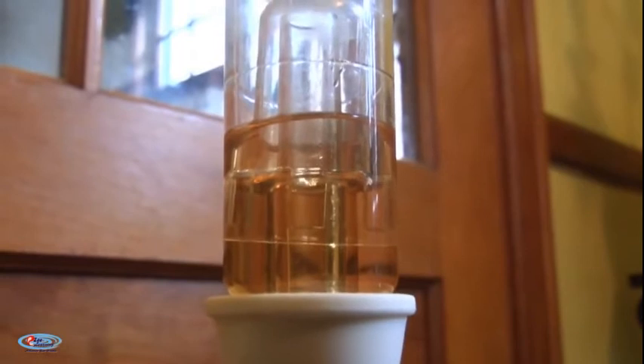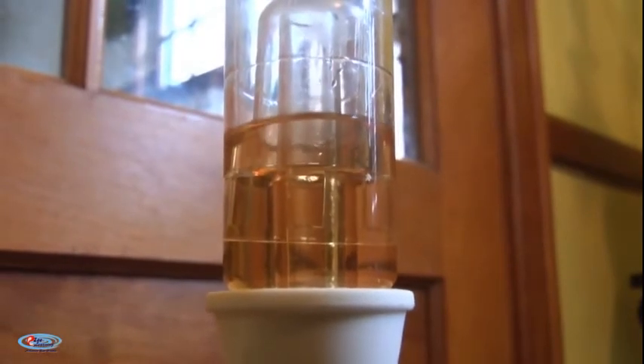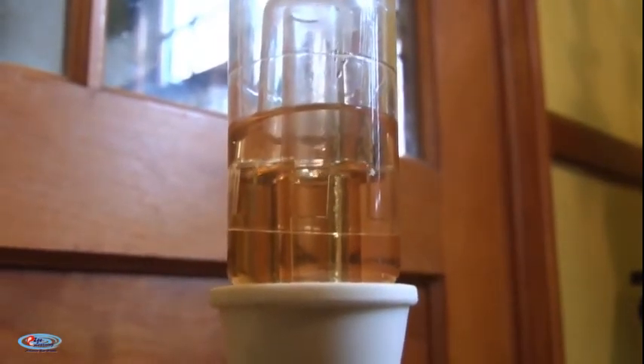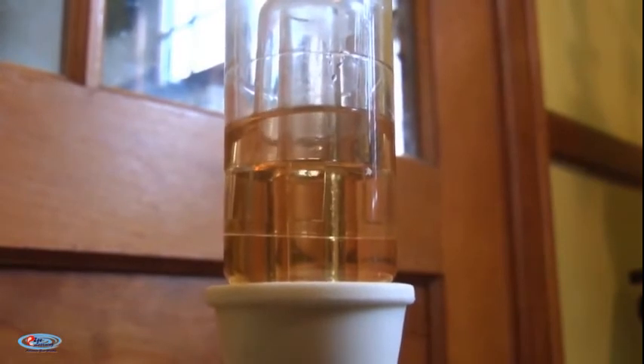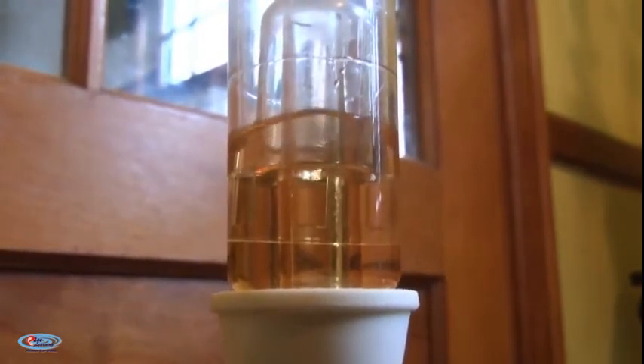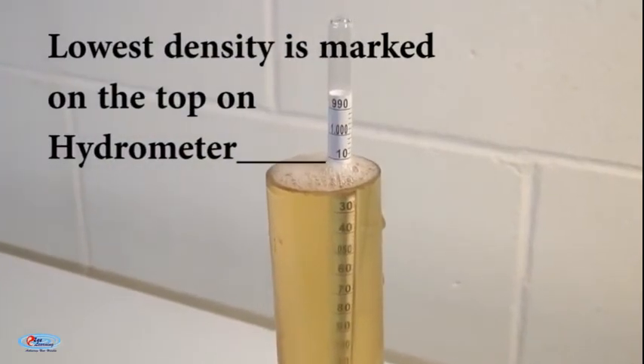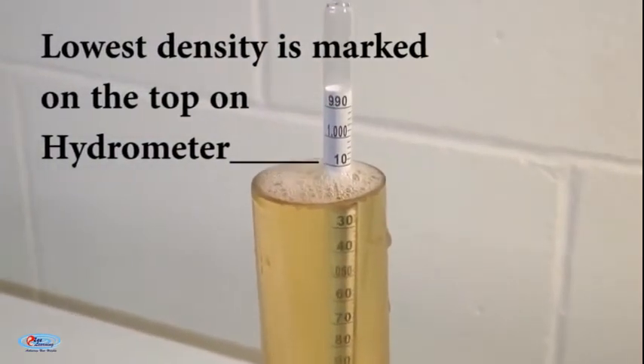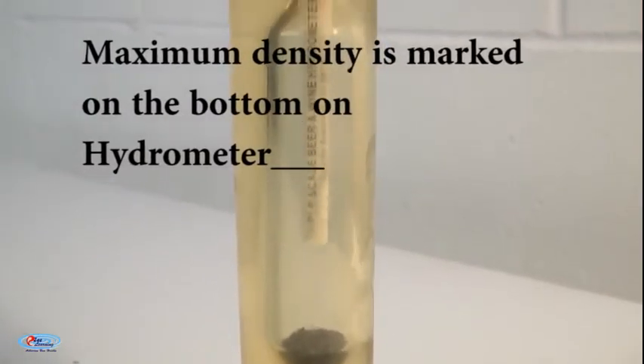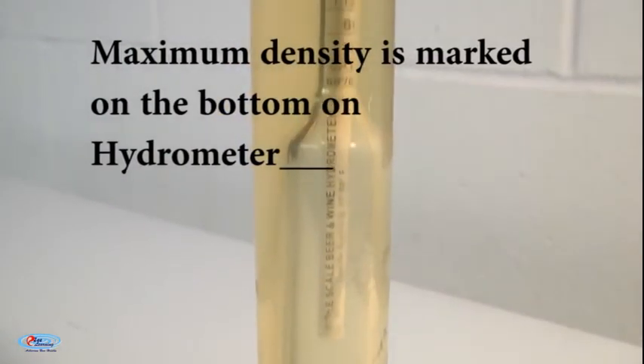Hence, it will sink less in a denser liquid so that it has to displace less volume of the denser liquid whose weight will be equal to the hydrometer. Thus, the lowest density is marked on the top of the stem of a hydrometer and the maximum density is marked at the bottom of the graduated stem.